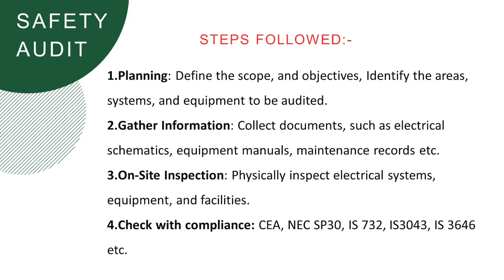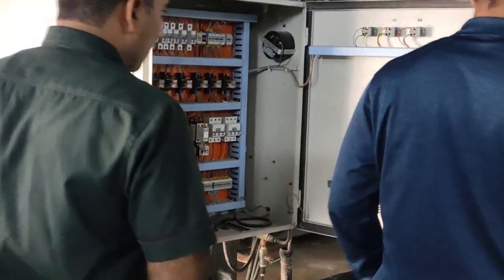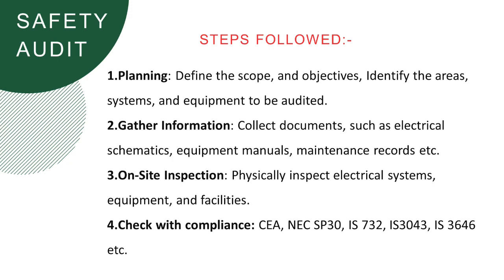The next step is on-site inspection. The auditor with a team will inspect your complete electrical system — how your electrical system is installed, whether your circuit breakers are okay, whether your distribution boxes and their circuit breakers are working properly, how your cables are routed, how your cable tray system is arranged, and whether your connections are okay or not. All these things will be checked by the team.